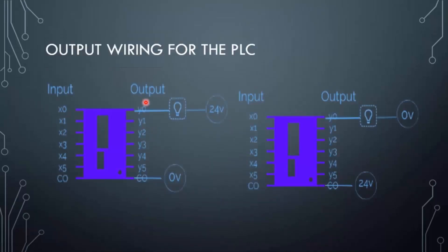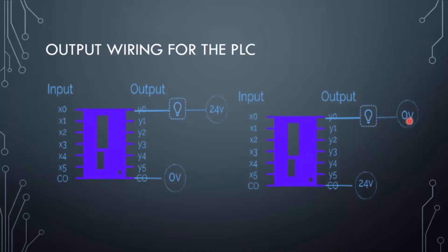Similarly, there are two types of output wiring. When 24 volts is connected with one of the outputs, the PLC output is said to be sinking. When 24 volts is connected with the common, the PLC is said to be sourcing. Keep in mind that whatever is connected at the common is internally connected with the output — for example, the common is internally connected with Y0 — and this is similarly true for the input side.